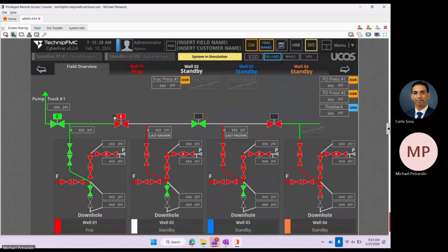The little E inside that box stands for energized. That simply means that you executed a valve move in Cyber. When you execute a valve move using automation, it will lock the handle into position, so if I walk up to it and physically try to move it, I can't. It's hydraulically locked, energized. As soon as you put the Cyber Hub or Mini Hub into manual mode, that's when the E goes away.